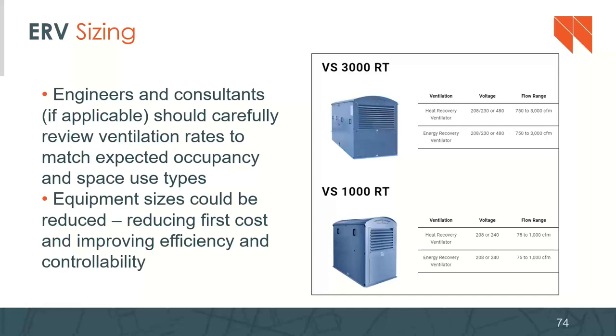In terms of sizing these things, the equipment sizes sometimes could be reduced, reducing the first cost and improving efficiency and controllability. So this is an example of a pretty large system versus the smaller system. And you can see the flow ranges: 750 to 3000 CFM for the system up top versus the 75 to 1000 CFM system. So you want to carefully review the ventilation rates so that you match the expected occupancy and the space use types.